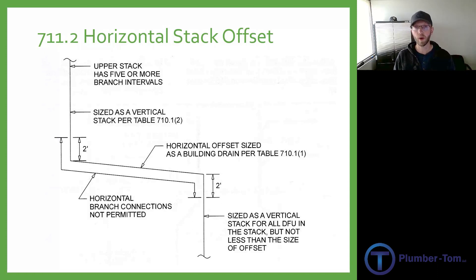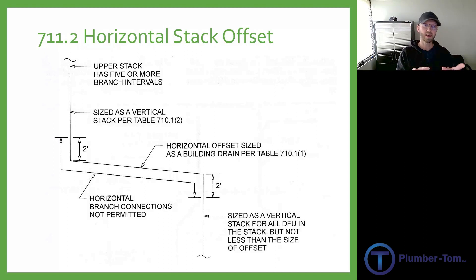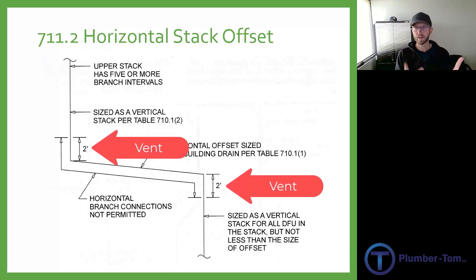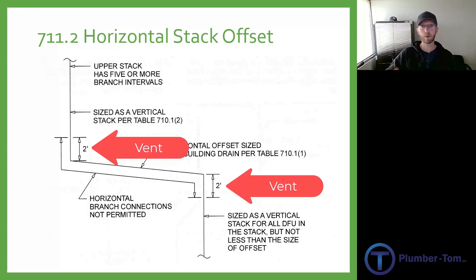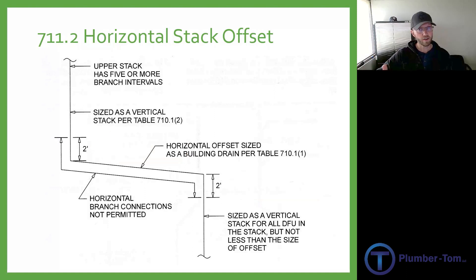7-11.2.1 also has an omission of vents for horizontal stack offsets. An offset like this would require some special venting, but that could be eliminated if the stack and its offset are one pipe size larger than required for the building drain. That'll give enough airflow and you would not have to provide vents.